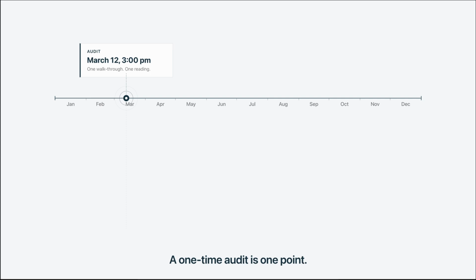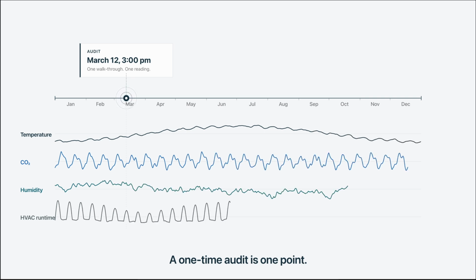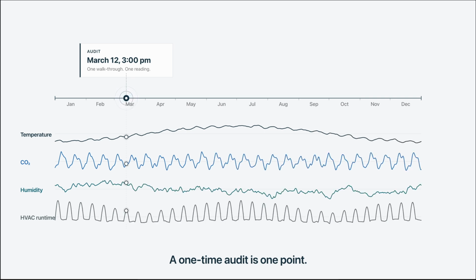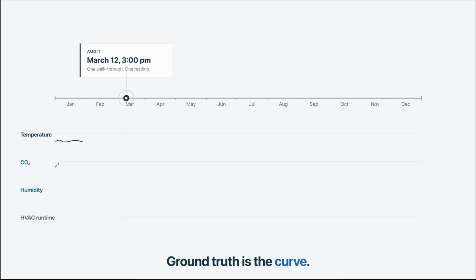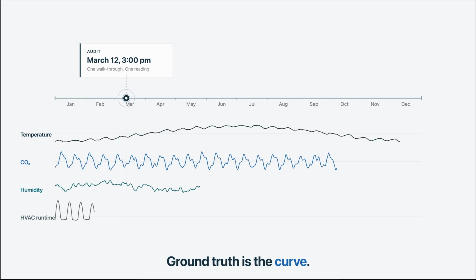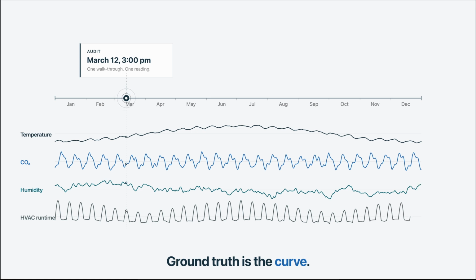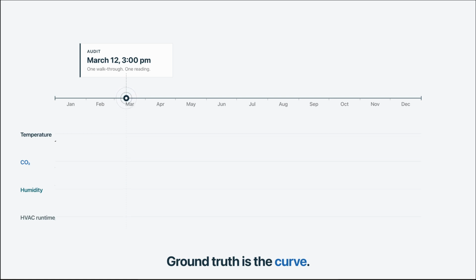The problem is that your building doesn't exist just in that snapshot. It's a 12-month, 24-hour behavioral pattern. An audit that happens on a Tuesday afternoon in March is not going to tell you much about what your building does on a Saturday night in August. It can't show you the conference wing that's been running full supply air every weekend for 2 years to meet the needs of a tenant that moved out some time ago and nobody remembered to update the schedule. It can't show you the zone where the setback is supposed to kick in at 5 p.m., but never has because an override was set once and forgotten about.